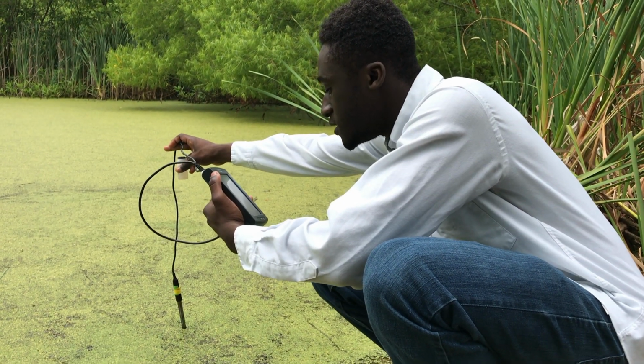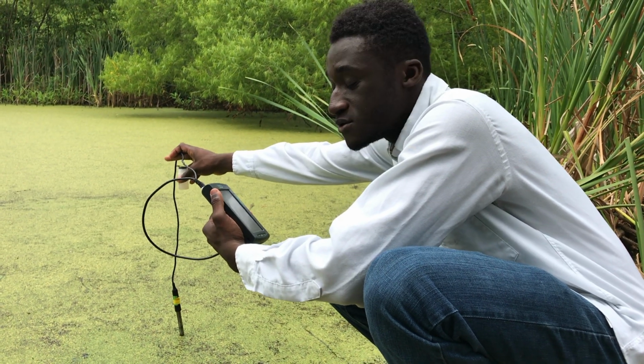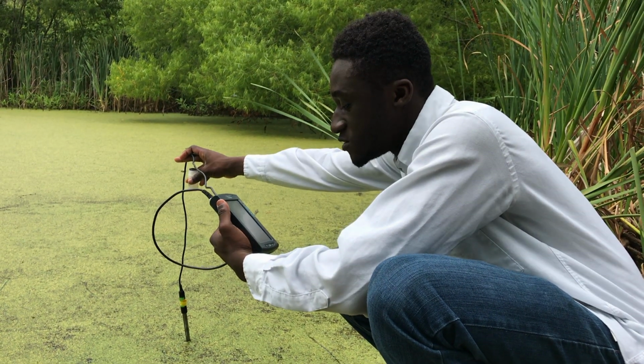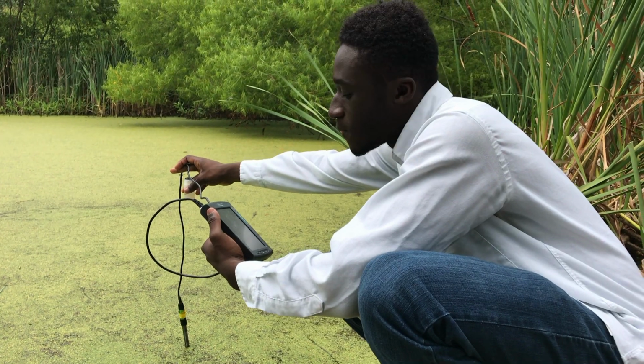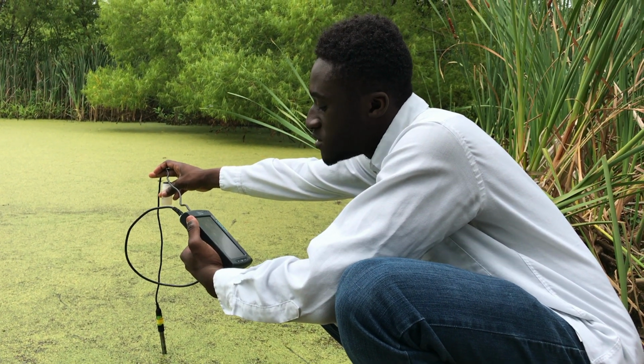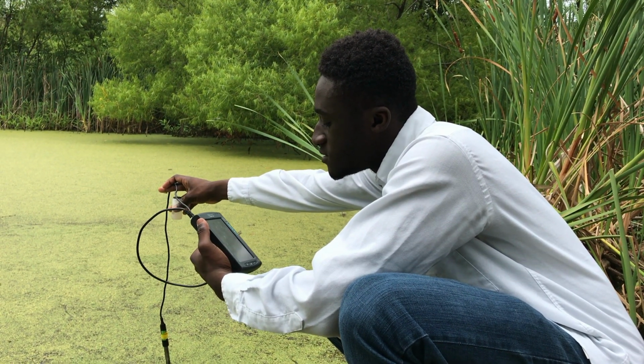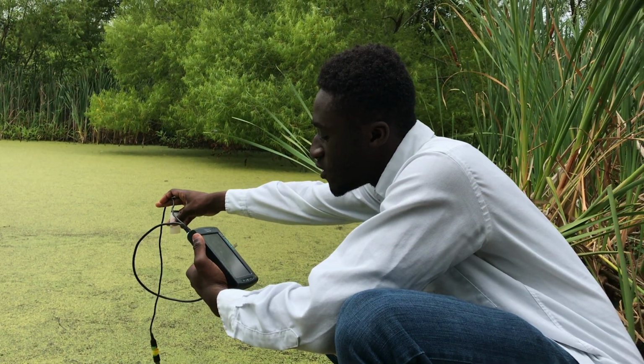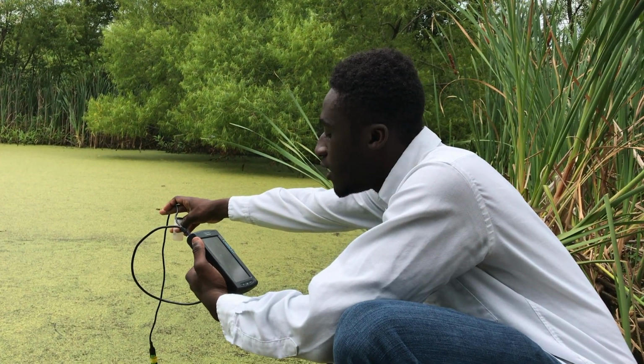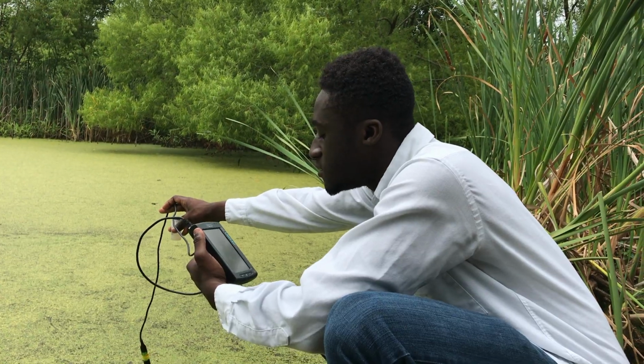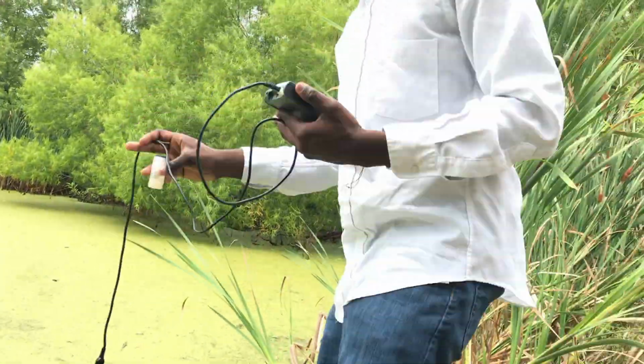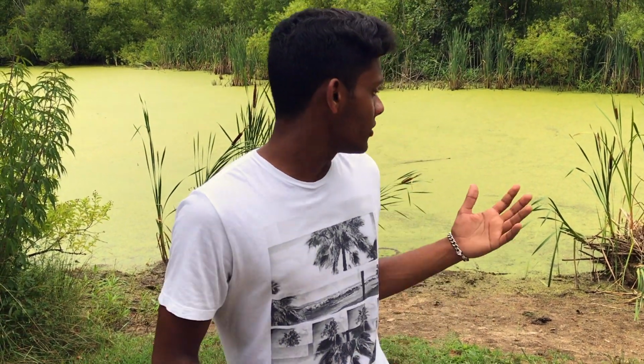We see we're getting a pH. It's fluctuating still, so naturally with any other probe, we want to make sure we wait until we get a stable reading. So now we see the pH is staying at 6.15, which is a fairly solid pH. You know, it's going to go up and down a little bit, but that should be our reading. So we can write this down, and then in general, you want to do maybe 1 or 2 more tests, but that's the process.